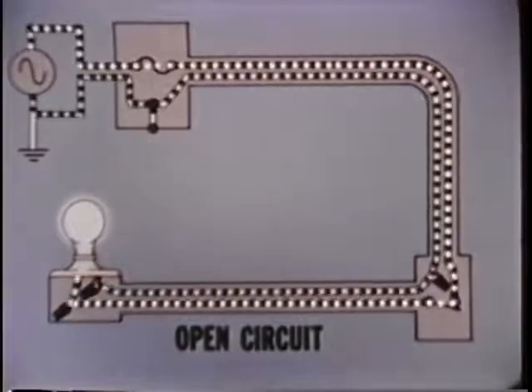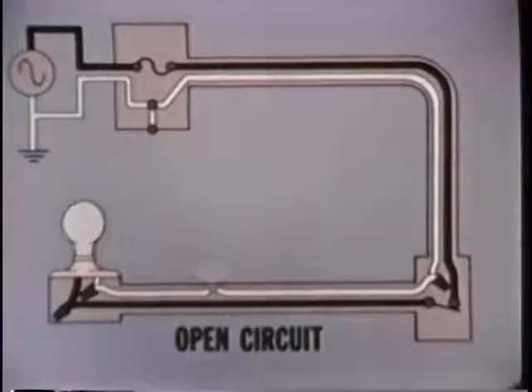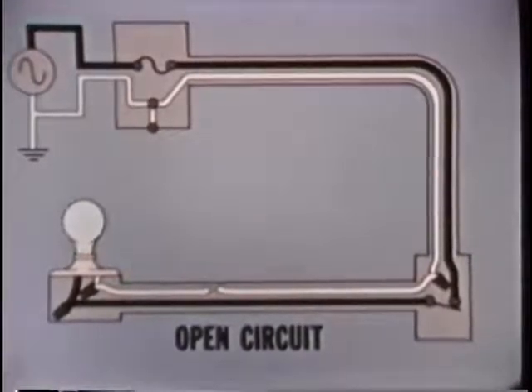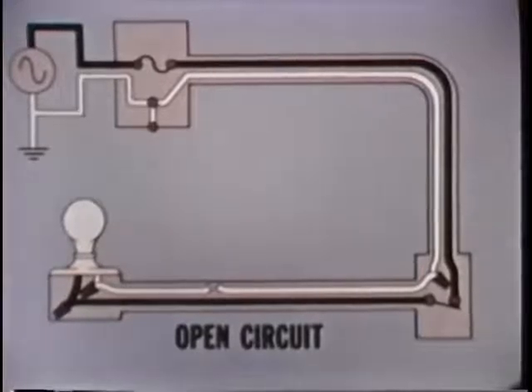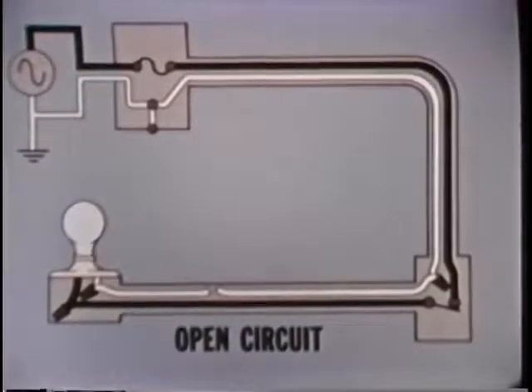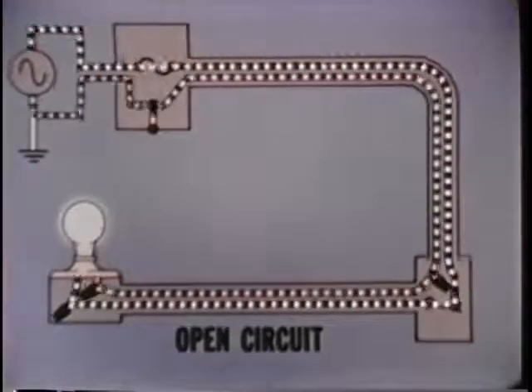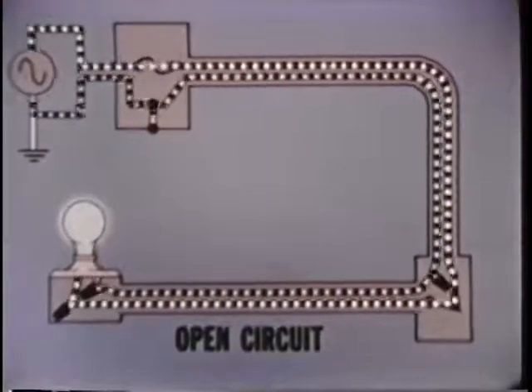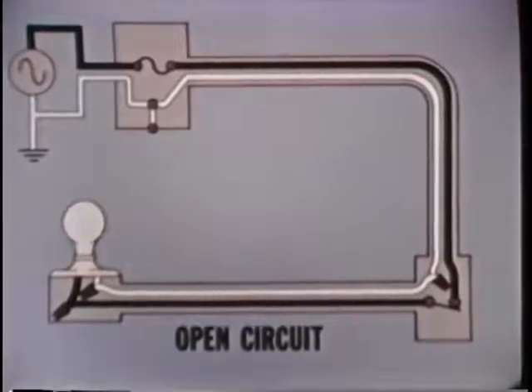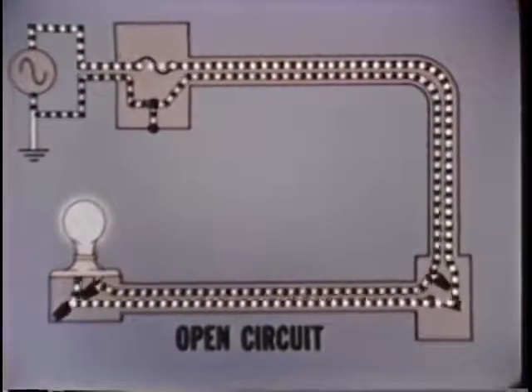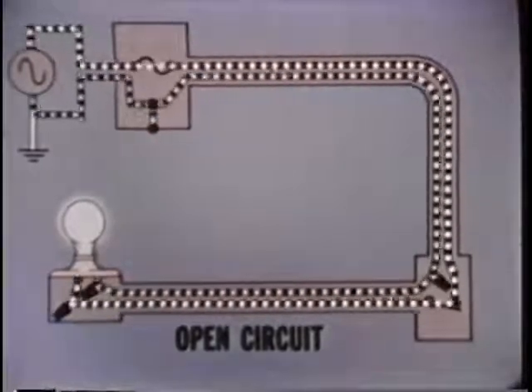An open circuit results when one or more conductors in a circuit become broken, burned, or otherwise separated to interrupt their continuity. An open circuit prevents any flow of current in the circuit. In this example, the neutral conductor has been broken to stop the current flow. If the hot conductor was broken instead, the effect on the circuit would be the same. If any part of this circuit fails, it breaks the continuity and stops the flow of current. Replacing the defective circuit component or repairing the broken wire restores the circuit to normal operation.